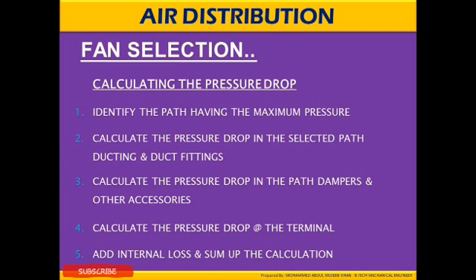Calculating the pressure drop. Identify the path having the maximum pressure. Calculate the pressure drop in the selected path ducting and duct fittings. Calculate the pressure drop in the path dampers and other accessories. Calculate the pressure drop at the terminals and internal losses and sum of the calculations.